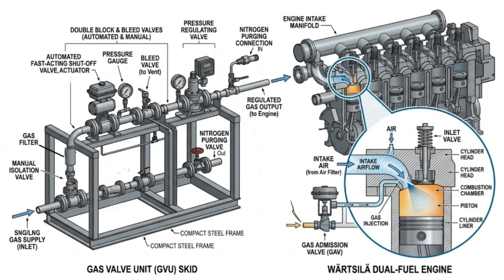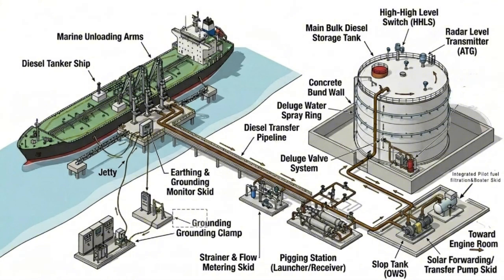After regasification, the gas enters the gas valve unit, or GVU, the final safety and control stage before the engine. The GVU regulates gas pressure and manages fuel isolation through a double block and bleed valve arrangement. During an emergency trip, the shutoff valves close immediately while trapped gas is safely vented to prevent hazardous accumulation. The system then stabilizes the gas pressure before distributing fuel to each cylinder through the gas admission valves. This controlled fuel delivery enables stable combustion and reliable engine operation in gas mode. Next, let us look at the independent diesel fuel system that supports backup operation.